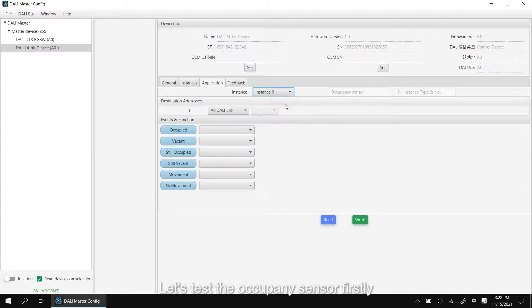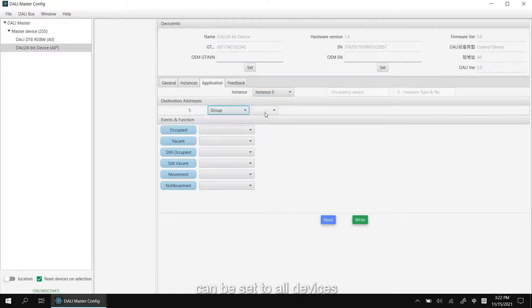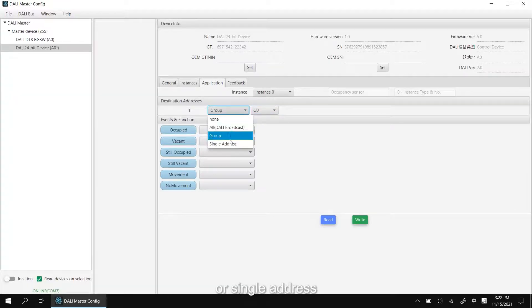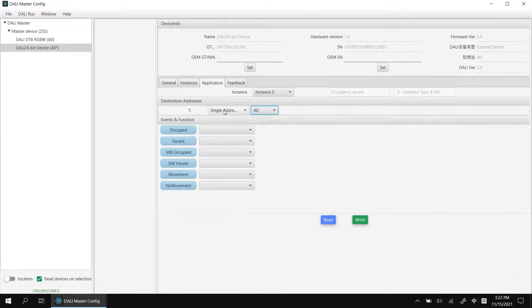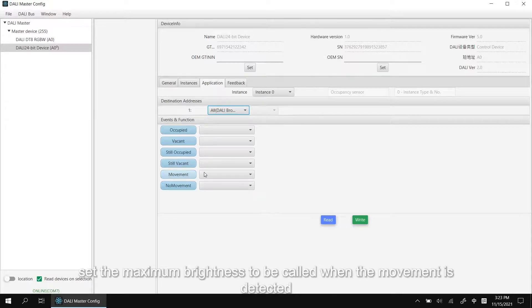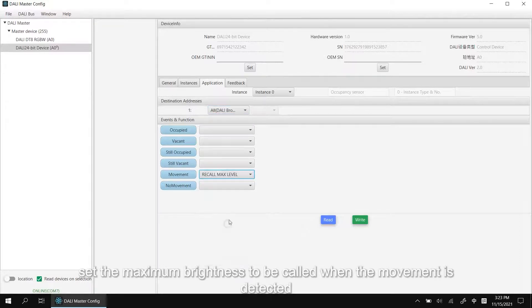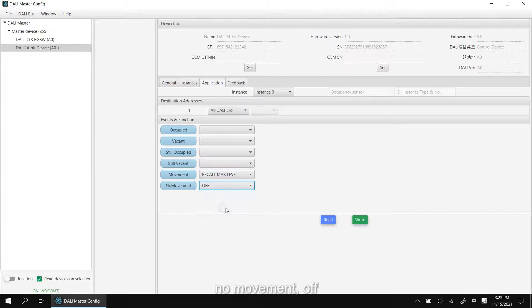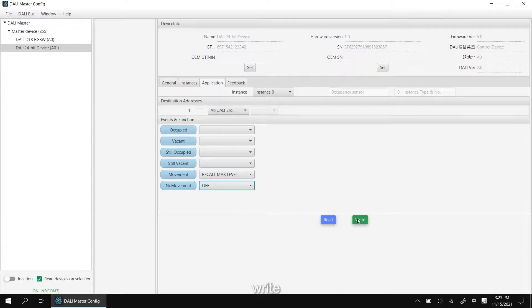Application is to set the feedback action when the event is triggered. Select the sensor unit. Let's take the occupancy sensor. Firstly, destination addresses can be sent to all devices, a group or single address. Set the maximum brightness to be recalled when the movement is detected. No movement, off. Write.